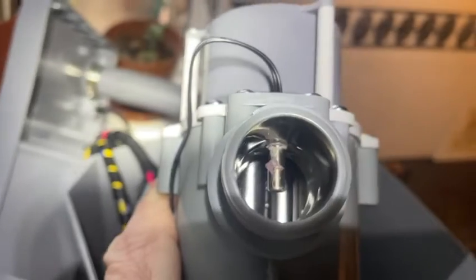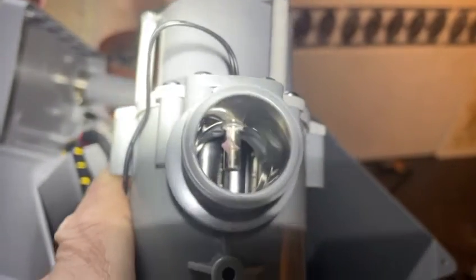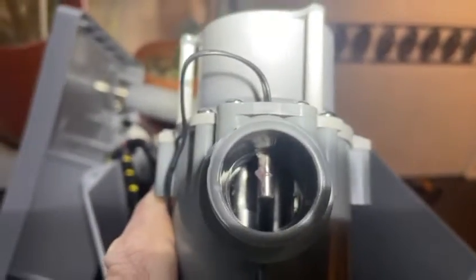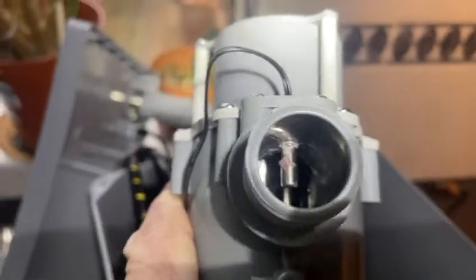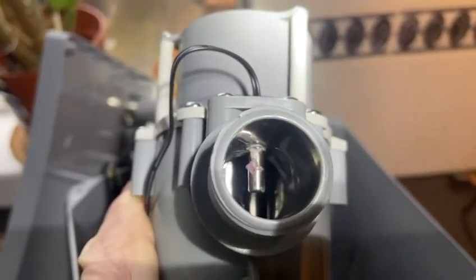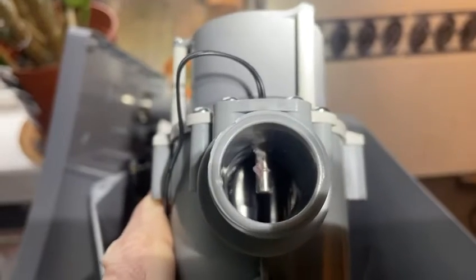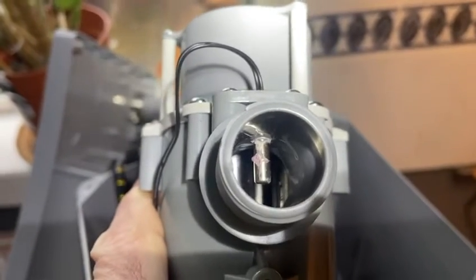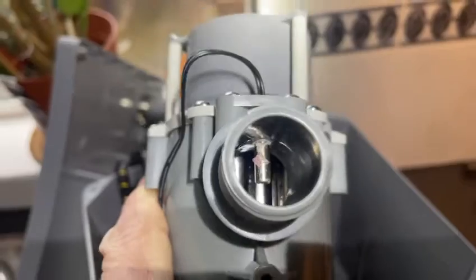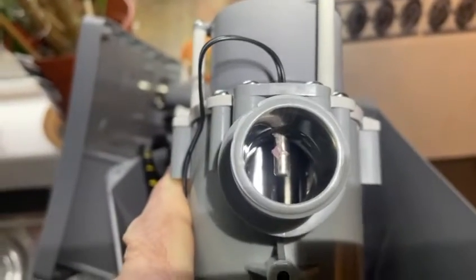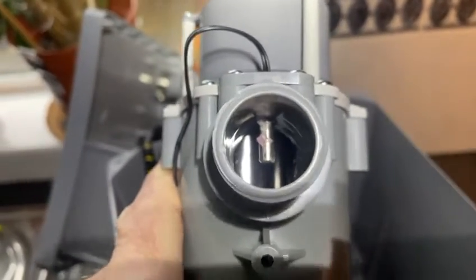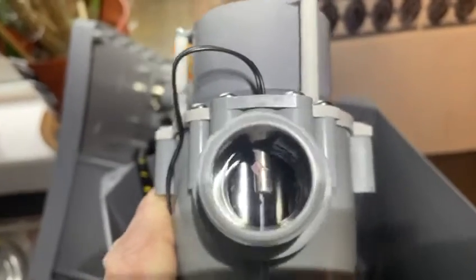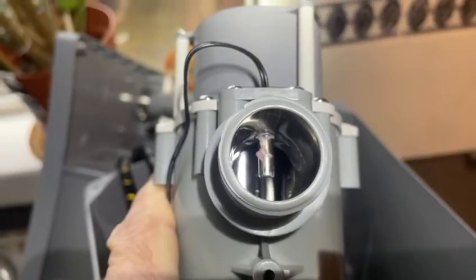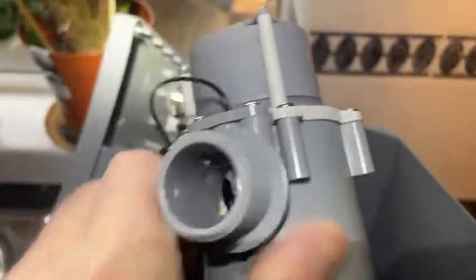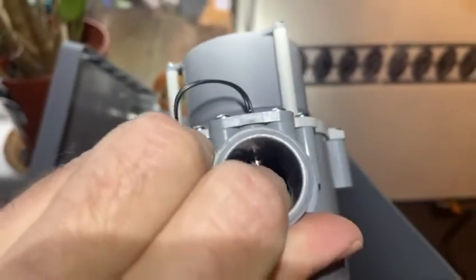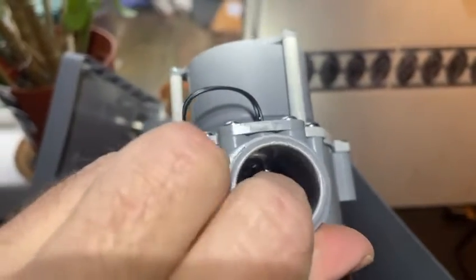You can see on that one it's starting to degrade - that's water ingressing into your temperature sensor, and that will foul over a short period of time. So what's happening is the water's ingressing into that probe, and when you're getting your SH, HO and SL error codes, it's because more often than not water's ingressing there and short circuiting this probe.